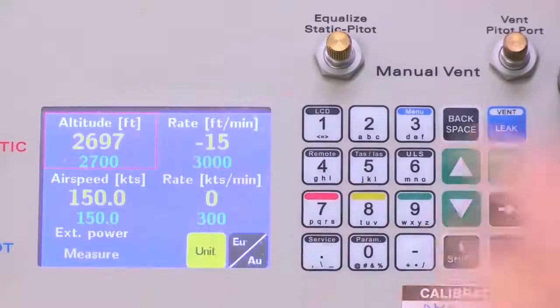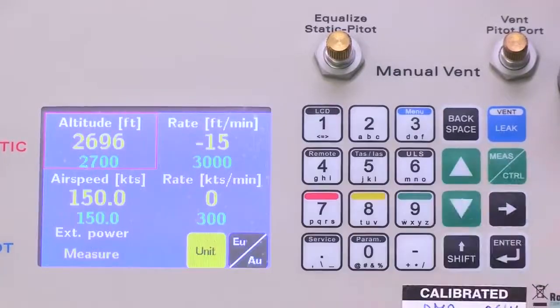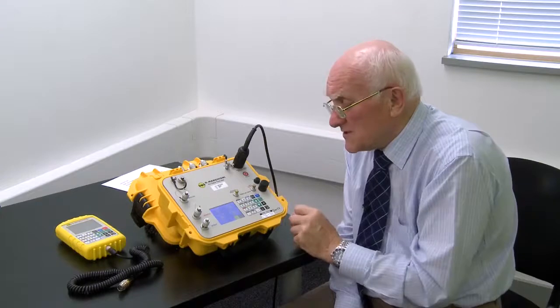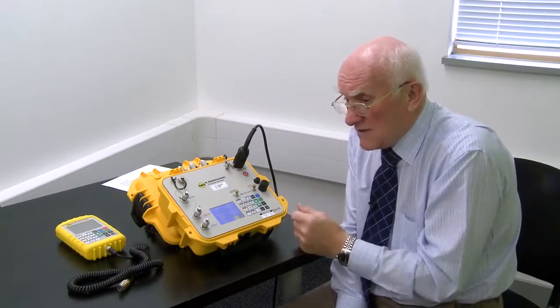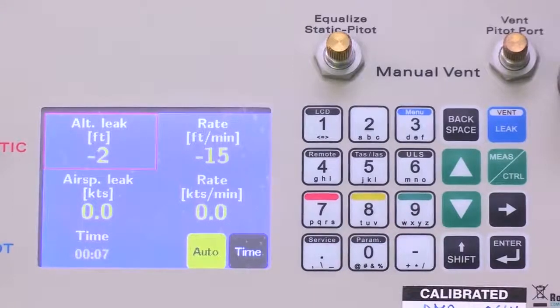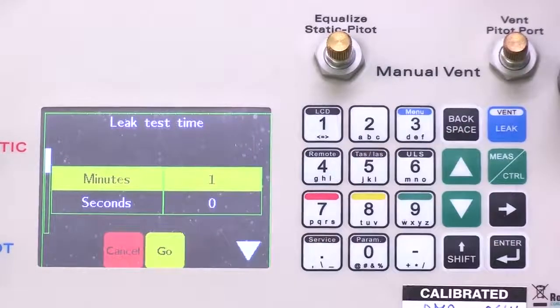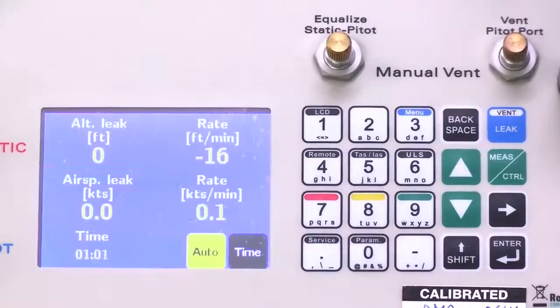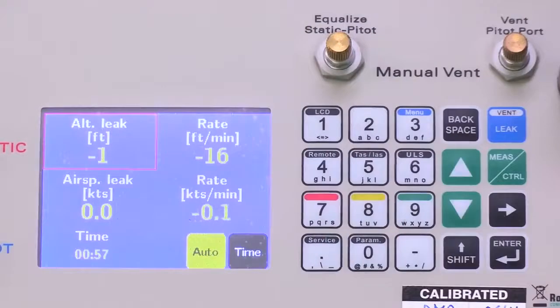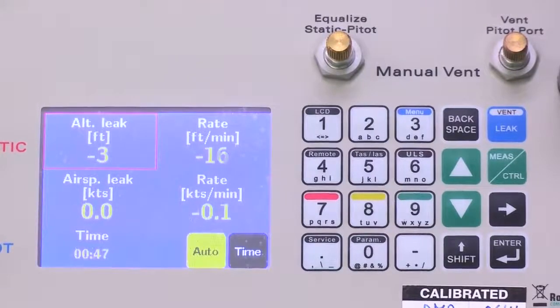We can use this to see whether we have any leaks, because if this was diving down at an enormous rate, you've got a leak and have to investigate it. If we go to leak test, you'll see it's now running up in seconds, and you could wait for the desired time, or go to time and set up how many minutes you want it to run for. At the moment it's set at 1, you can make it whatever, press go, and it's now going to time down - no longer just up but down. At the end of that time you'll have the values you need in terms of altitude drop and airspeed drop, which can then go into your manuals or test routines.